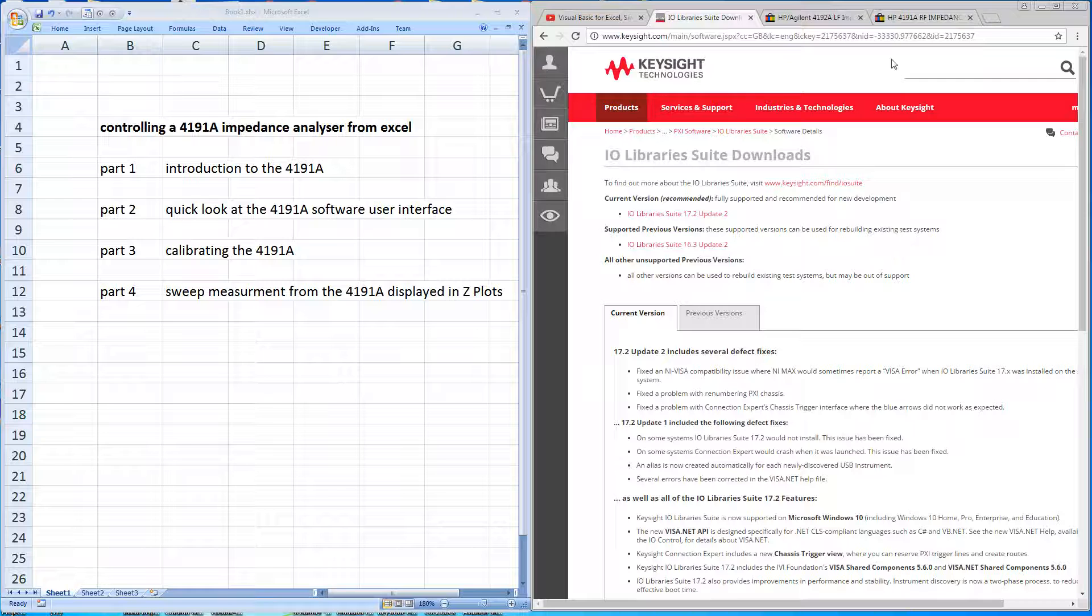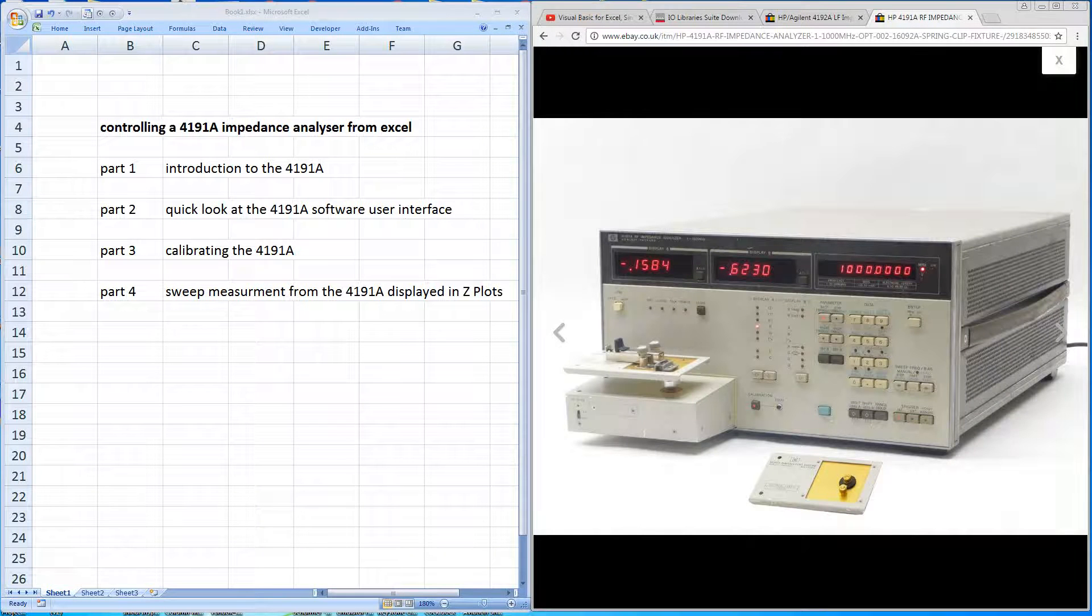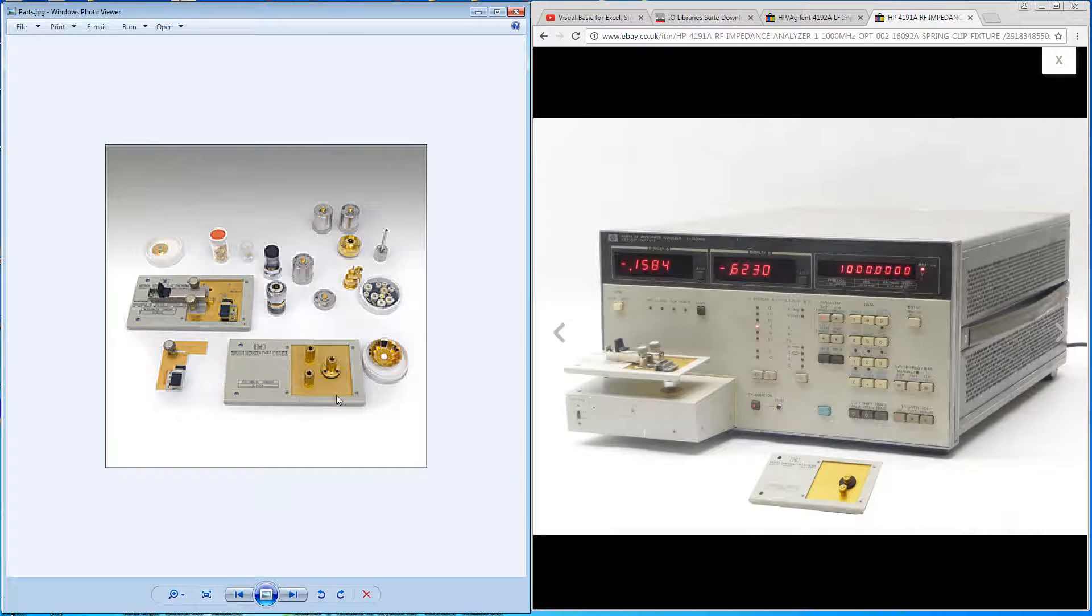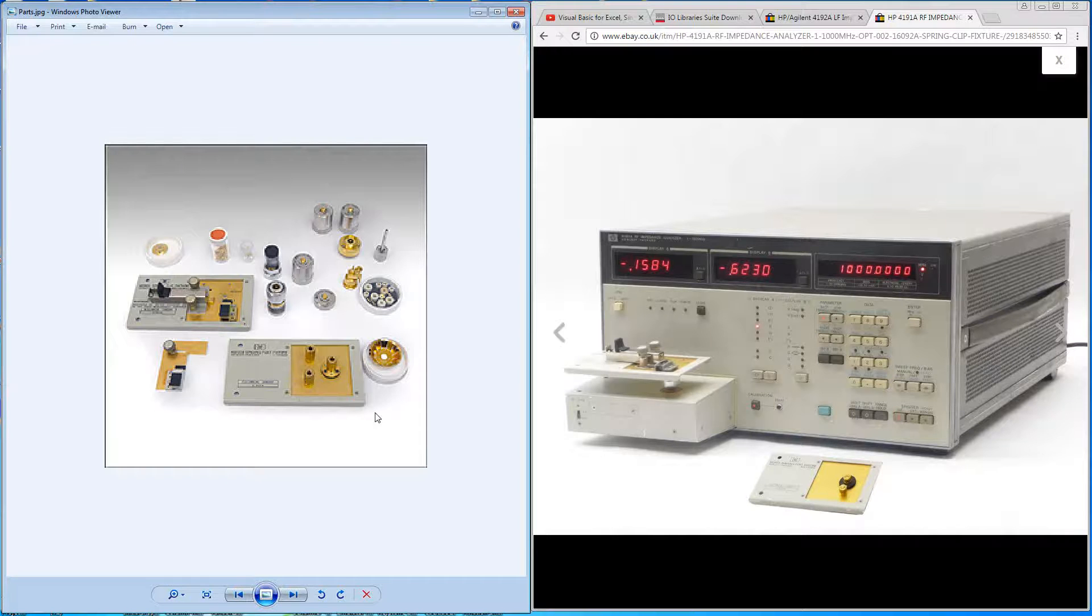The analyzer comes with a number of test fixtures, and also the calibration standards for the machine. If you're intending to work with the machine, it's important you obtain as many of these as possible. To obtain the accuracy of the machine, you really need to be working with these sort of test fixtures.